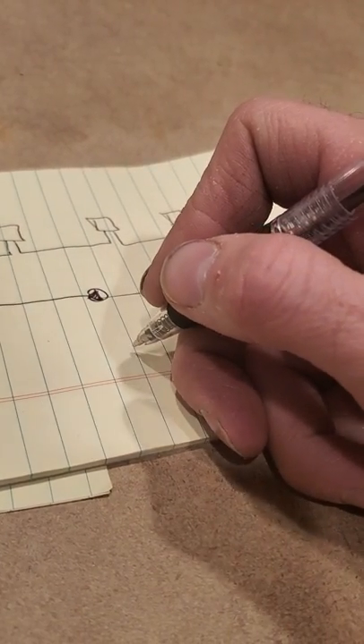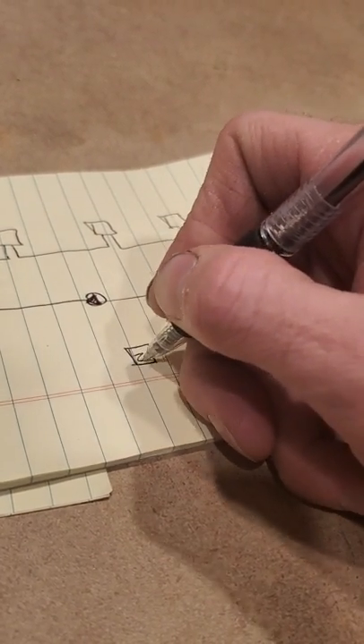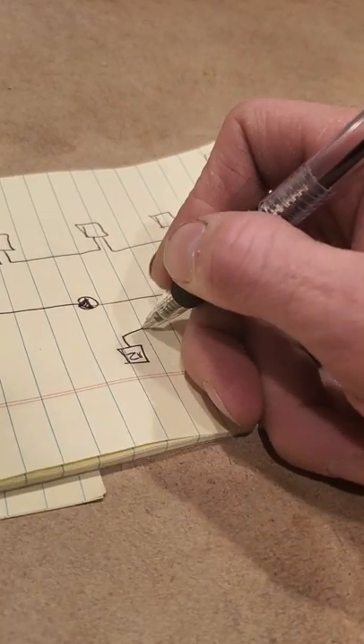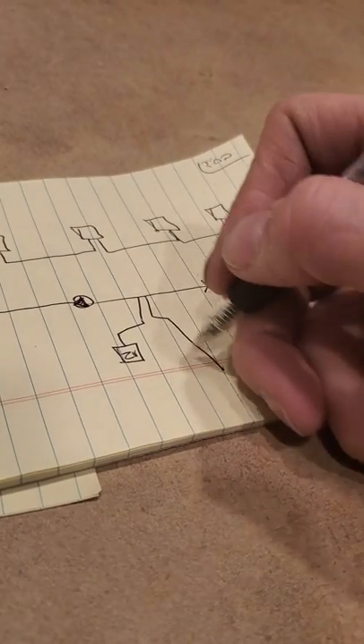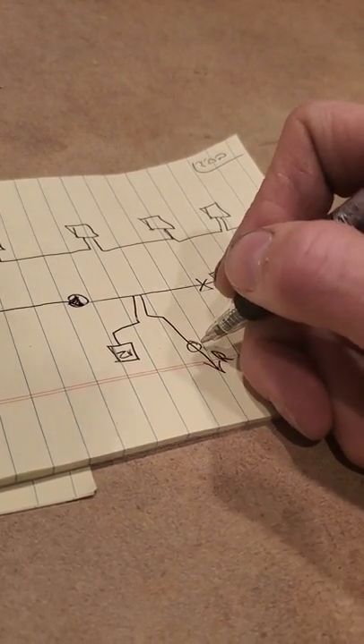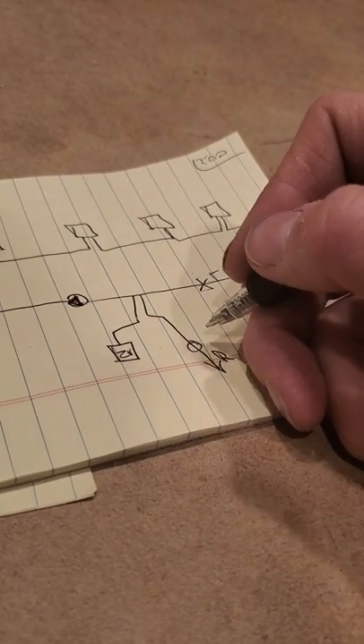What we did was over here, took a zone valve. Instead of looping it out to one of the baseboard zones, connect it to a closely spaced T's and cause an injection. Here's the return, back to the boiler. You can put a globe valve over here, a ball valve, or anything you'd like. And this is coming from the boiler, from the manifold.